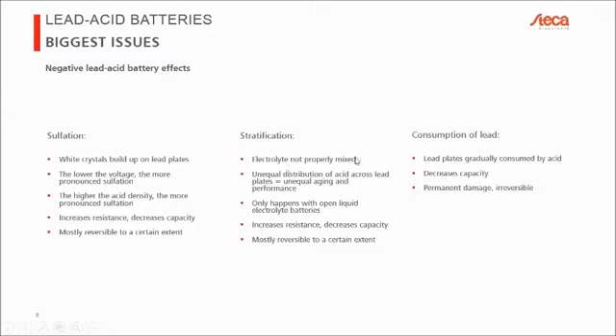Then in the middle we have stratification. What that simply means is that we have layers of electrolyte. I believe water ends up on top and electrolyte on the bottom, since the electrolyte is heavier. If you do not have a uniform distribution of your electrolyte mixture, then of course the top of the battery will behave very differently to the bottom of the battery.